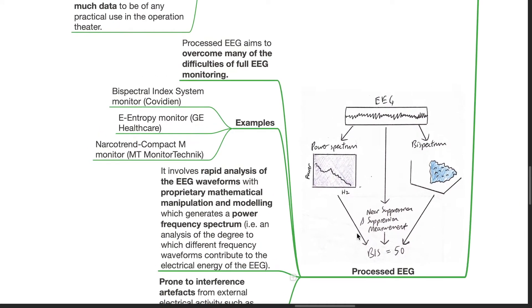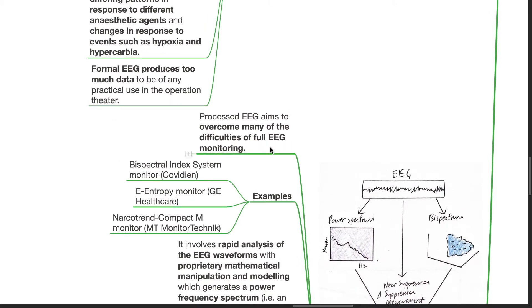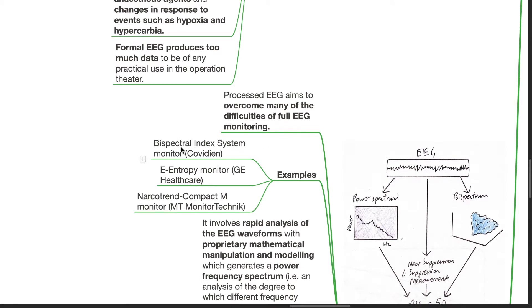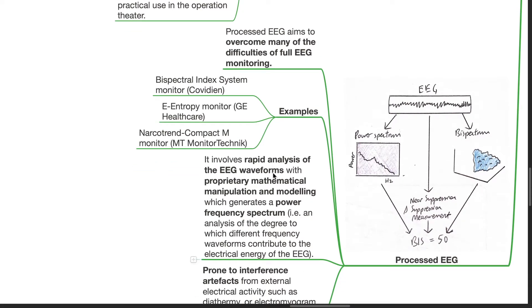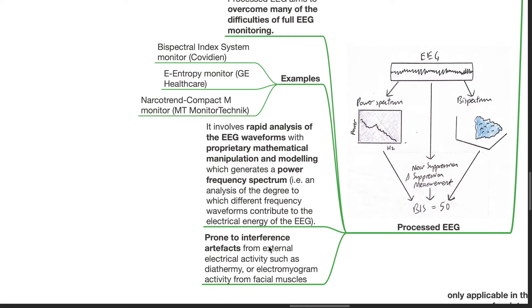Processed EEG aims to overcome many of the difficulties of full EEG monitoring, which includes the bispectral index (BIS) system, e-entropy monitor, and Narcotrend compact monitor. It involves rapid analysis of EEG waveforms with proprietary mathematical manipulation and modeling, which generates a power frequency spectrum — an analysis of the degree to which different frequency waveforms contribute to the electrical energy of the EEG. However, it is prone to interference artifacts from external electrical activity such as diathermy or electromyogram activity from facial muscles.